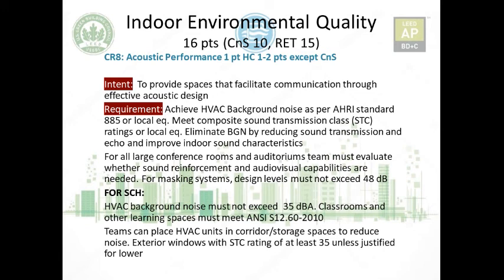Sound reinforcement is typically considered for meeting, open office, public or presentation spaces that seat more than 50 people, depending on their function. A simple amplification system may meet the criteria for smaller and simpler spaces. And sound masking is a technology that uses artificially produced sound, such as white noise, to cover or mask unwanted sound.